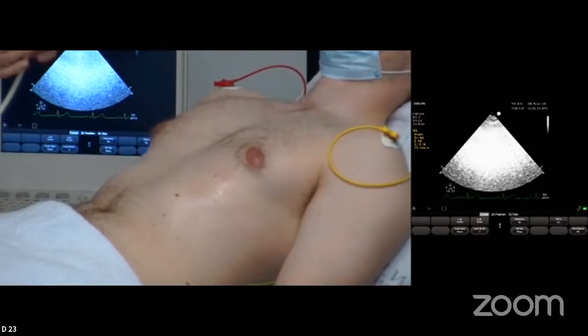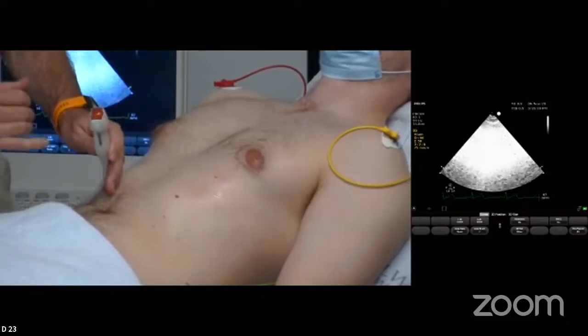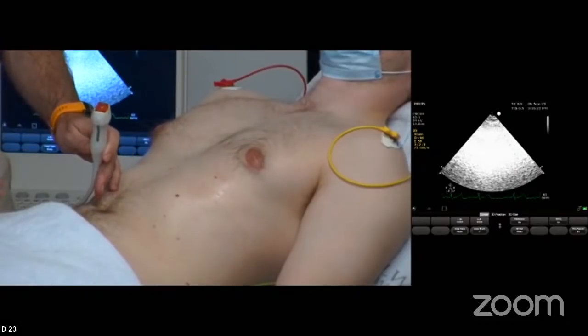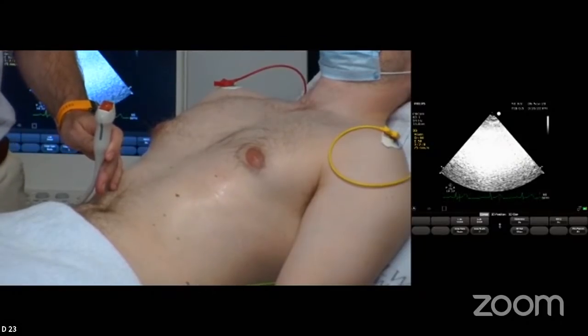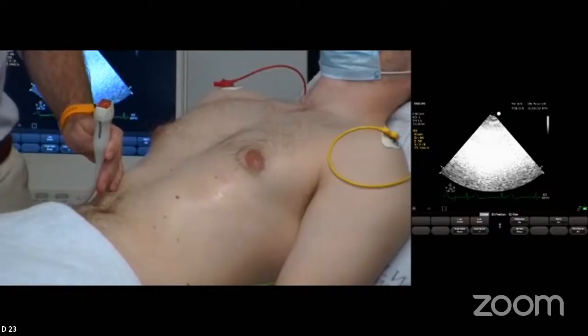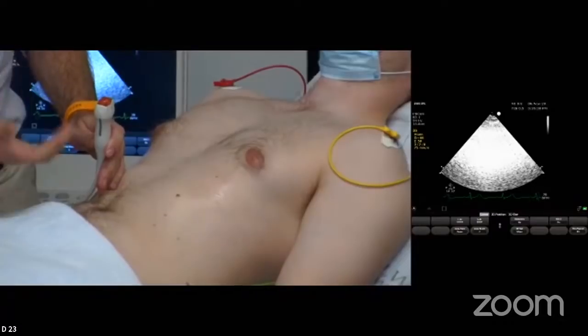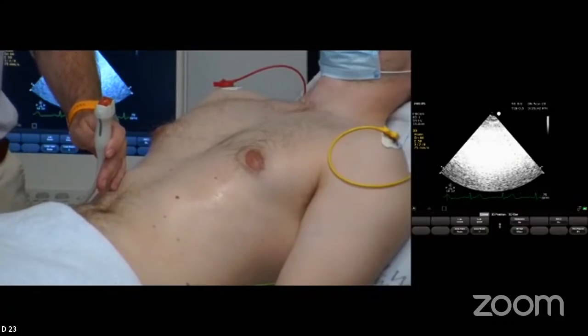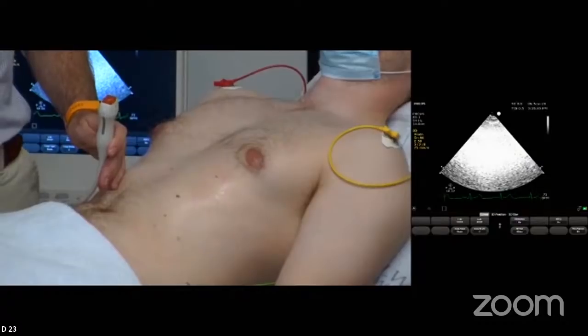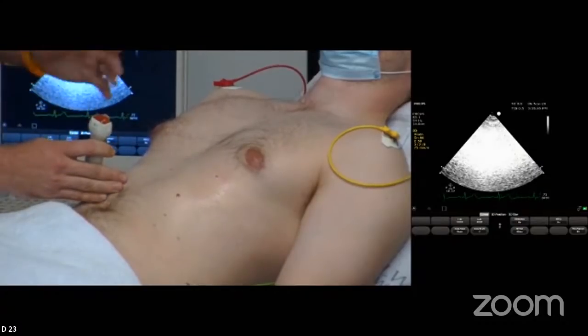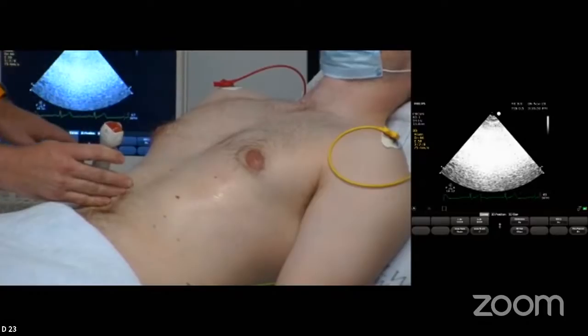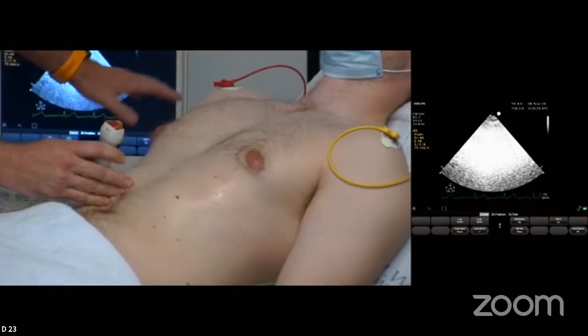So just a reminder, if we are able to zoom in on the probe: a traditional phased array probe is a low frequency probe, remembering that low frequency penetrates deeper. High frequency probes, linear probes, are generally used for vascular access, and they only penetrate to a maximum of 6 centimeters or so, depending on the probe. With a phased array, you're going to penetrate deeper, to 20, 25 centimeters. I'll talk to you as I go, explaining the use of all these complex knobs that you see on the machine behind me.